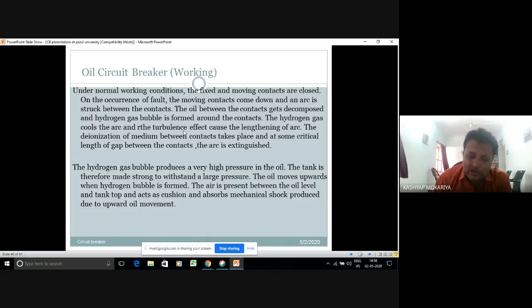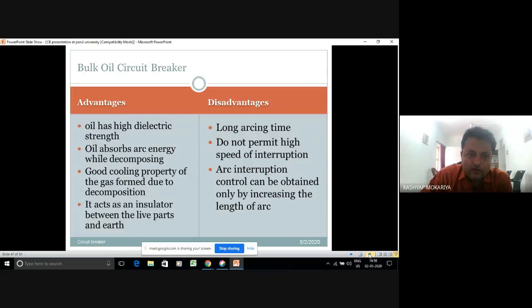So the hydrogen gas bubble produces a very high pressure in the oil. The tank is therefore made strong to withstand a large pressure. The oil moves upwards when the hydrogen bubble is formed. The air present between the oil level and the tank top acts as a cushion and absorbs the mechanical shock produced due to the upward oil movement. So, bulk oil circuit breaker: oil has a high dielectric strength, oil absorbs arc energy, it has good cooling properties, and it acts as an insulator between the live part and earth.